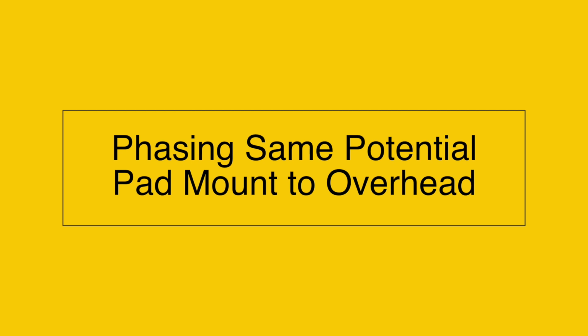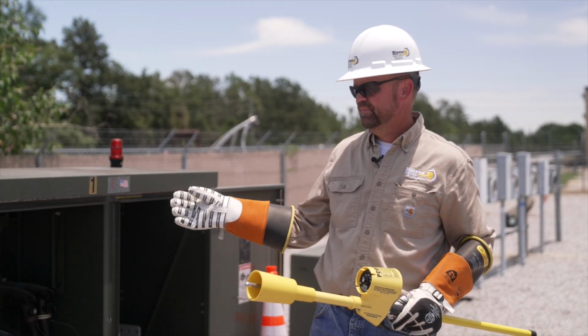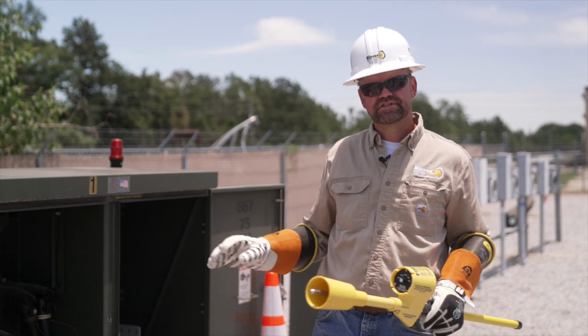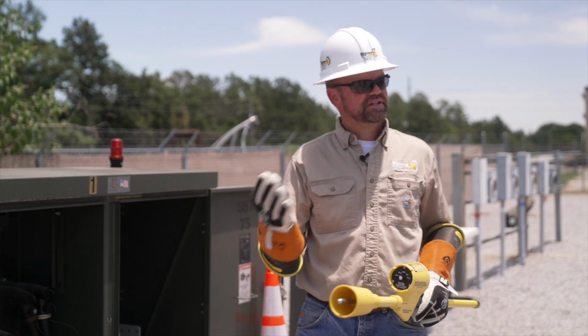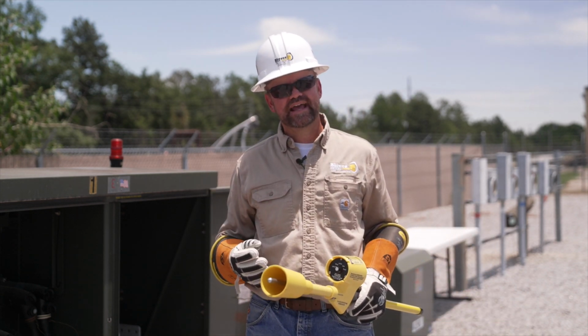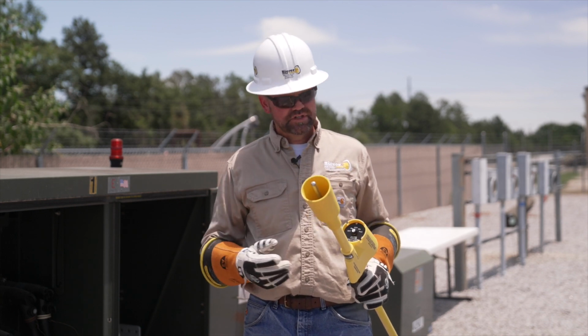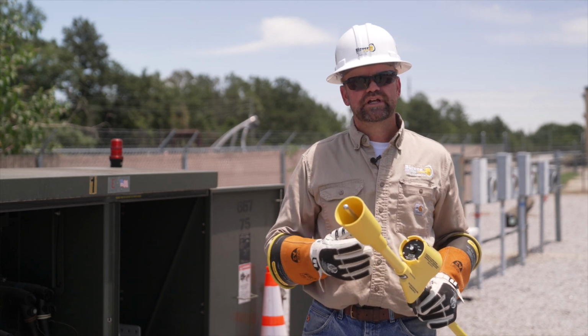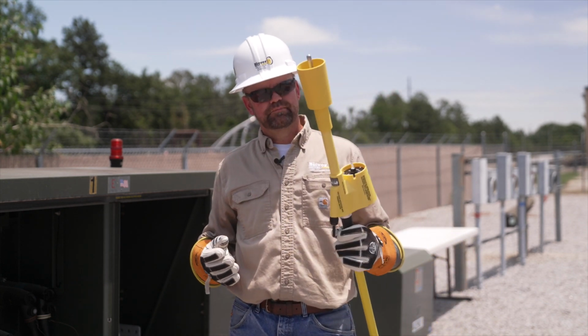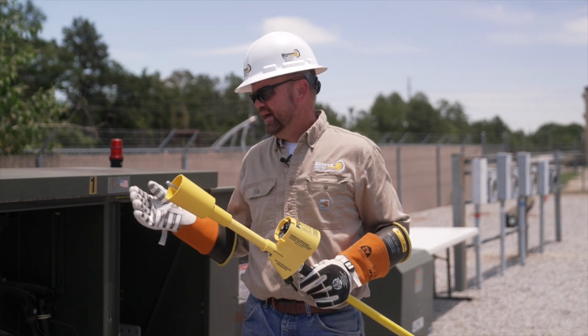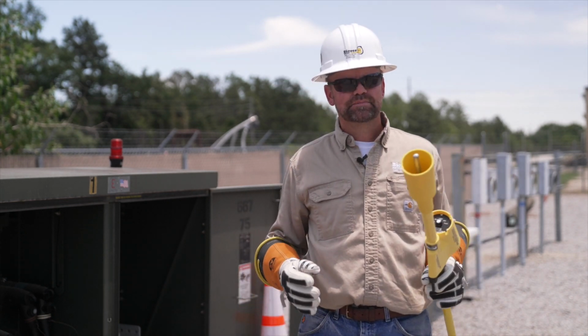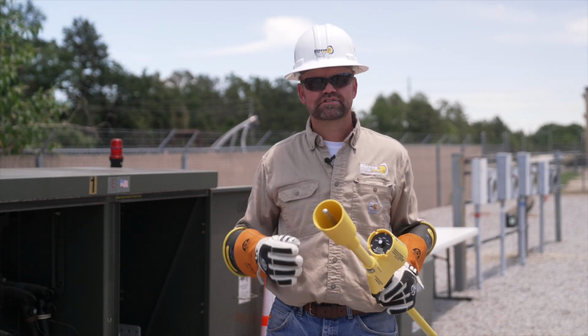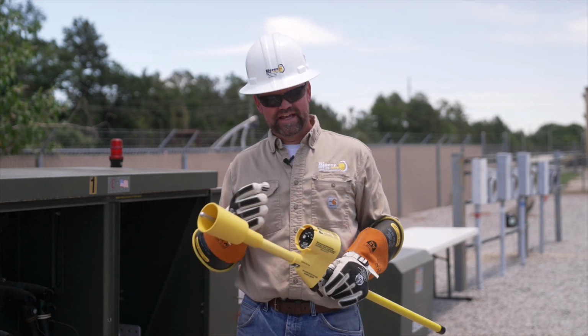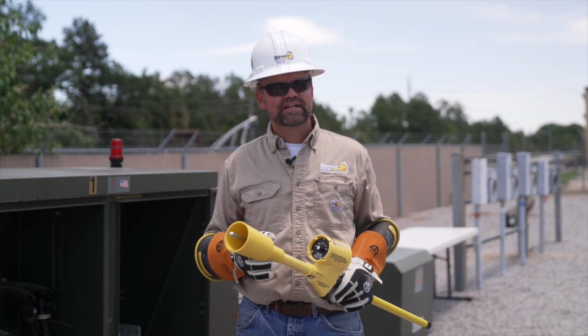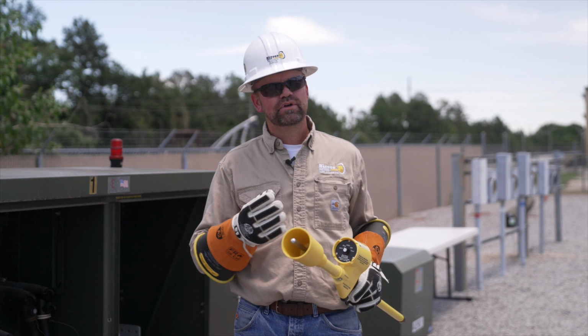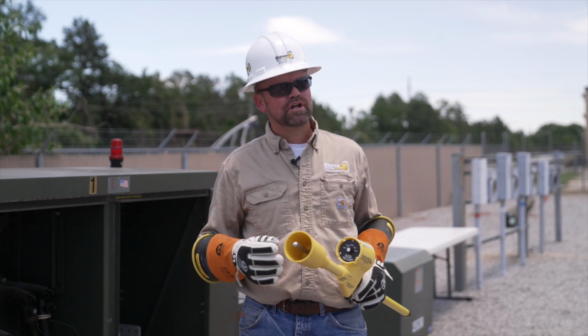Okay, the next demonstration, I'm going to phase from my 13.8 kV to ground pad mount to some overhead conductors. It all is the same potential, but what I'm going to demonstrate is some of the distance this tool can phase. In other words, I can actually get over 100 feet away. So this is an FCC licensed tool. In other words, we're only allotted so much power output per the FCC with this device. So I can't output a lot of power and phase a mile away or something like that, because you start affecting other customers that use wireless and remote devices. So rule of thumb is if I can't see the other probe, give yourself about 100 feet. If it's line of sight, in other words, I can actually see the other probe, you can approach about 300 feet. So in this scenario, we're going to be about 50 feet away.